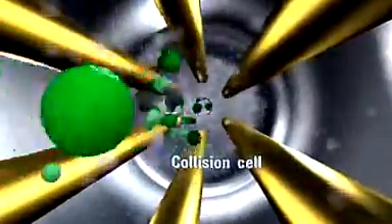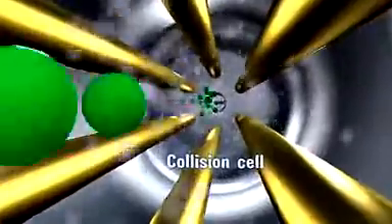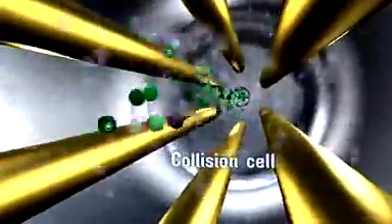In the hexapole collision cell, precursor ions strike collision gas molecules generating product ions and neutral fragments. Linear axial acceleration and high collision gas pressure ensure that all ions exit the collision cell with nearly identical energy.